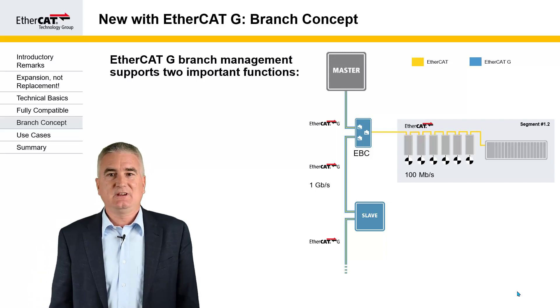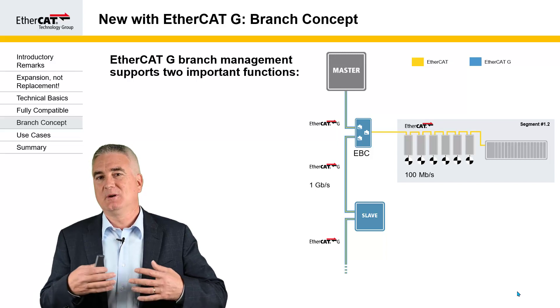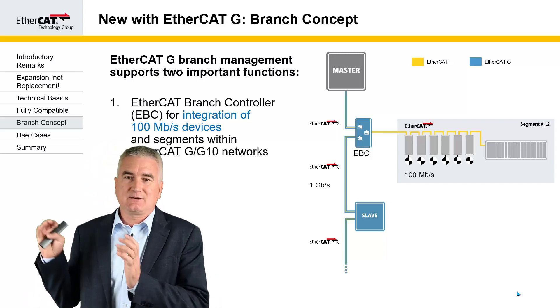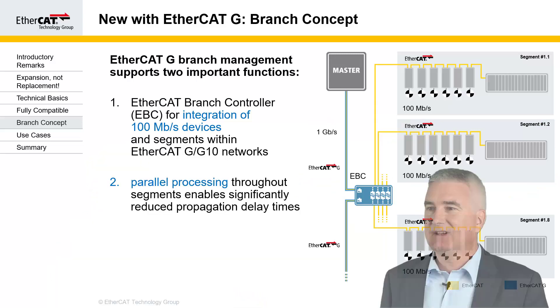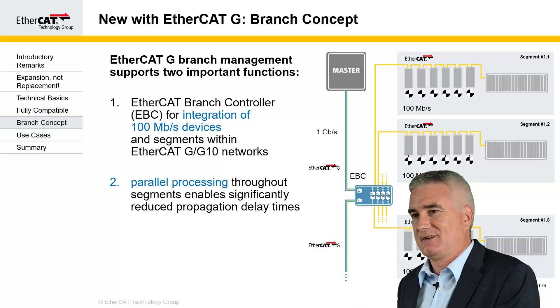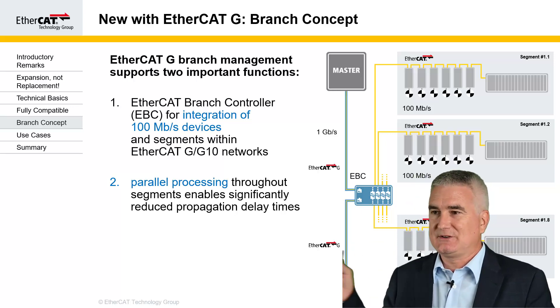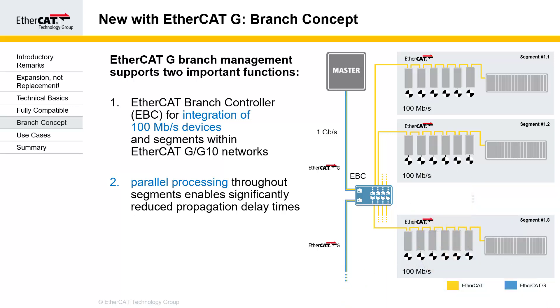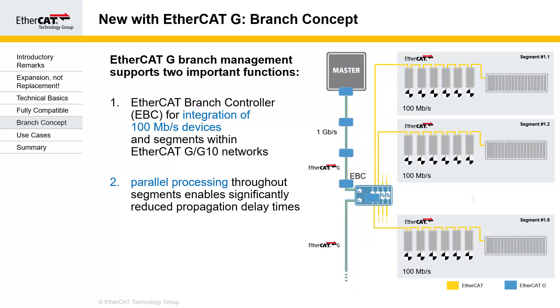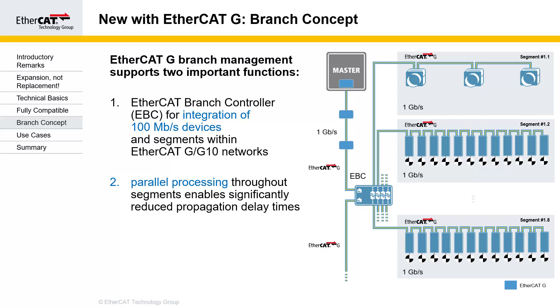What is new with EtherCAT-G is the so-called branch concept. This branch management gives us two important additional functions. First, it allows us to integrate 100 megabit segments into a gigabit backbone or a 10 gigabit backbone. Secondly, it gives us the ability to run multiple segments in parallel. Unlike before, where the frame went through all the devices and back to the master, now we have separate frames for each segment running in parallel. Frames arrive in gigabit mode; if segments underneath are 100 megabit, they are converted into 100 megabit frames, and on the way back changed to gigabit again and sent back to the master. This works as well if the segments underneath are gigabit segments — then the frames remain gigabit throughout.